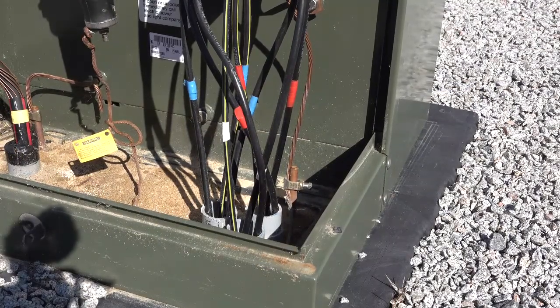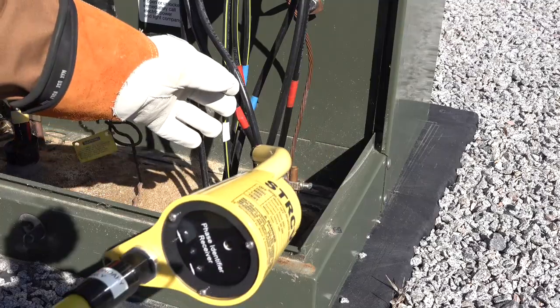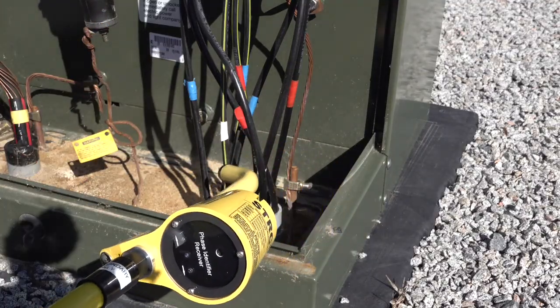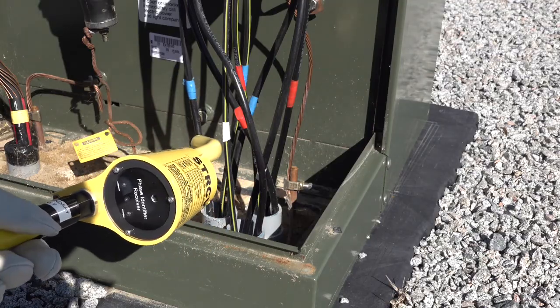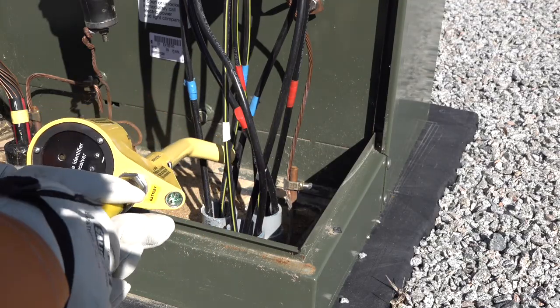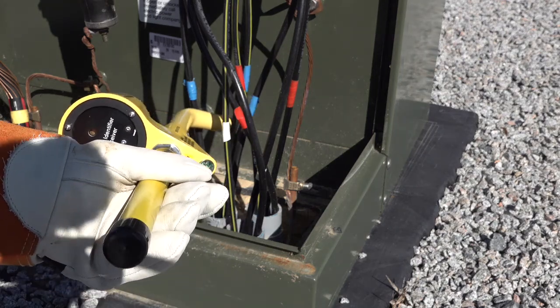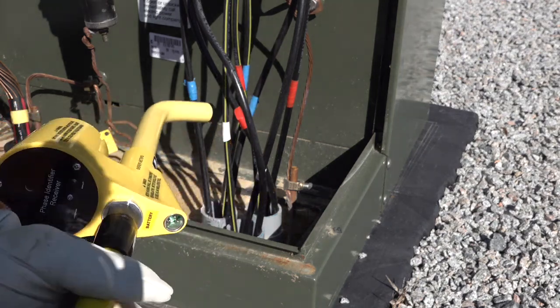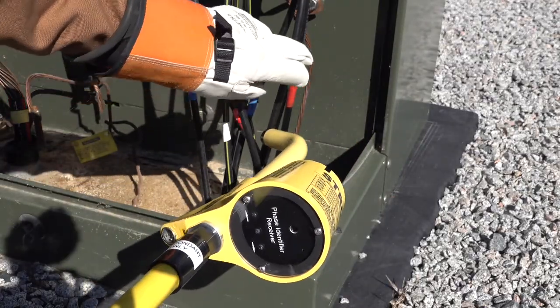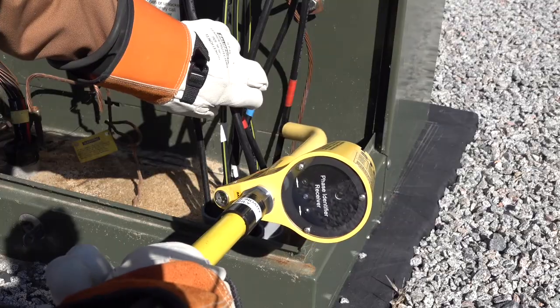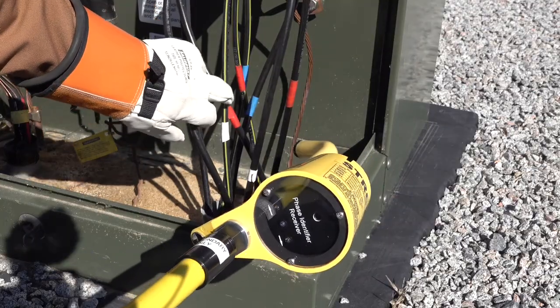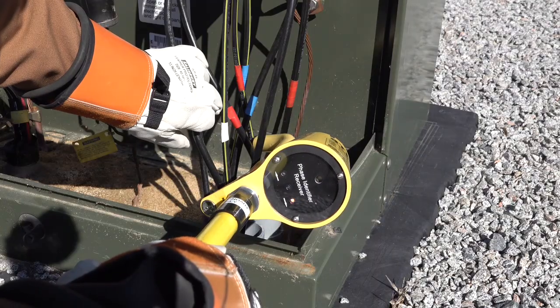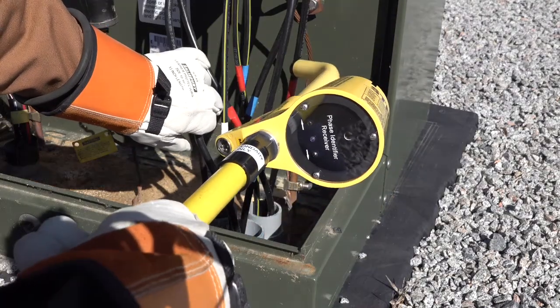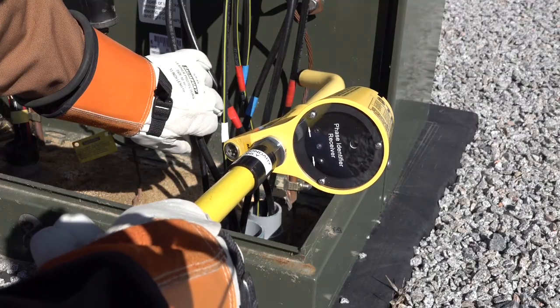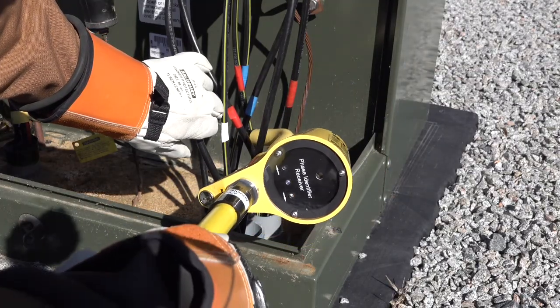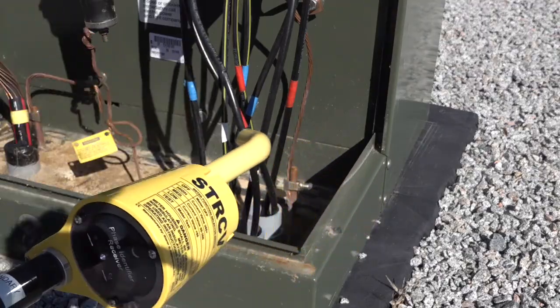We also want to be able to identify the neutral conductor, and we will perform this in the same manner as we did when we identified the hot conductor. Since the black lead of the ST800 is attached to the neutral, we're looking for a pulse in the opposite direction as the hot, so the pulse should be pointing down. Here is the hot conductor pointing up, and once we find the neutral, it's pointing down in the opposite direction as the hot pointing up. So now we've been able to identify both conductors.